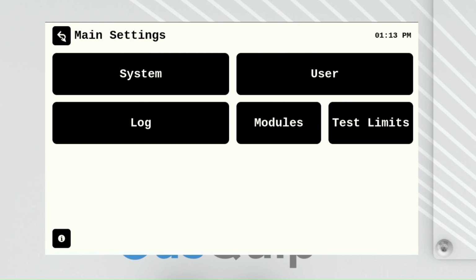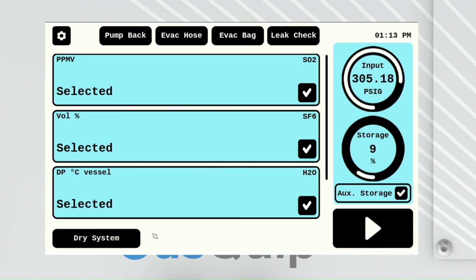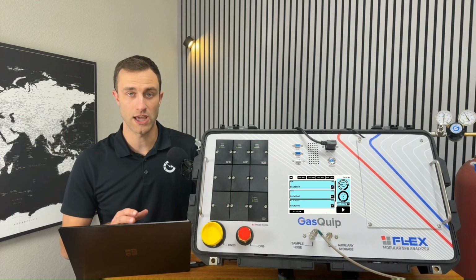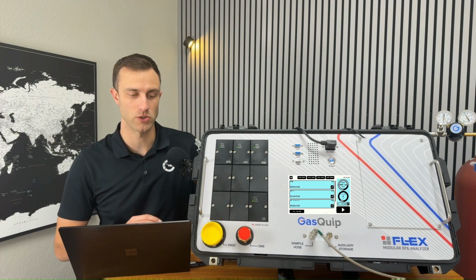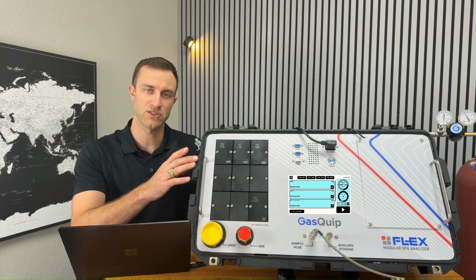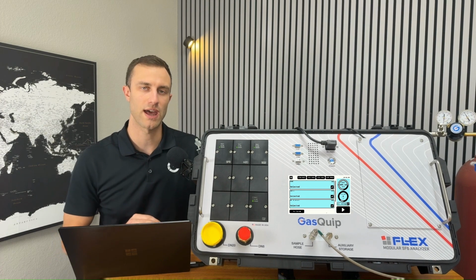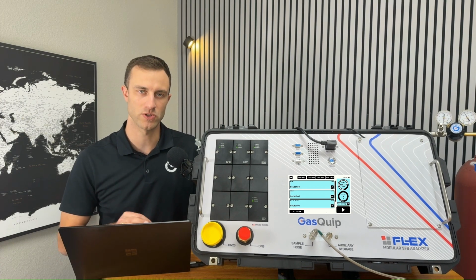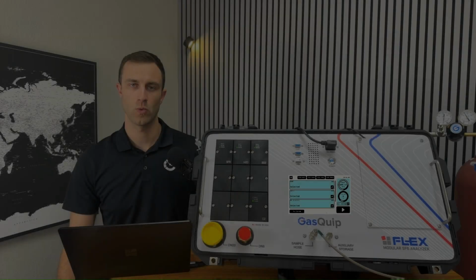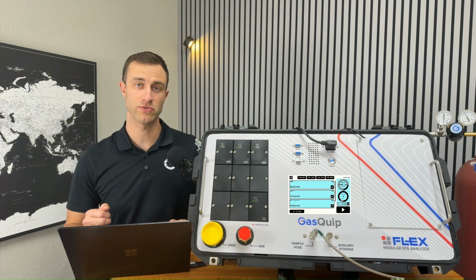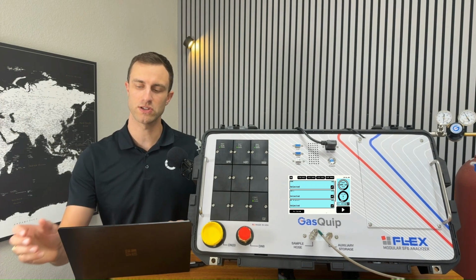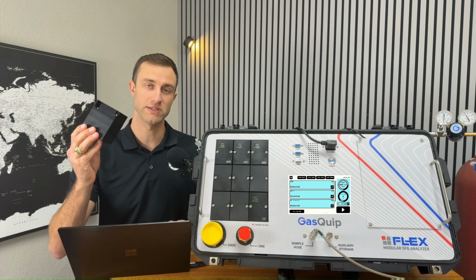Again, on the front screen, on the very bottom, if you do have a module that's out of calibration, you will get a system message down here to let you know which module is out of calibration. And also, the standard intervals for the current generation modules are: SF6 is every 2 years to replace, and the SO2 and H2O modules are every 1 year. When a module's calibration interval is up and it's time to replace it, we will send you the replacement module.